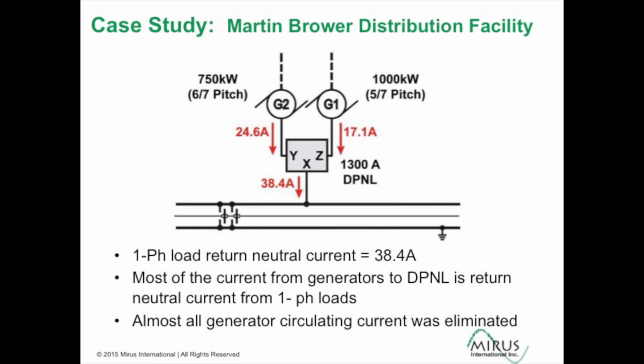This current going back through the neutral is current from phase to neutral loads in the system, which has to have a return neutral path. So there was a substantial reduction in the neutral conductors. The temperatures of neutral conductors dropped dramatically, and the generators were offloaded of this excess 180 hertz currents.